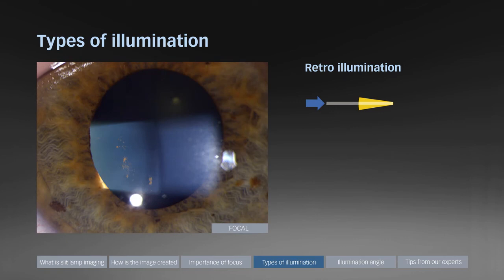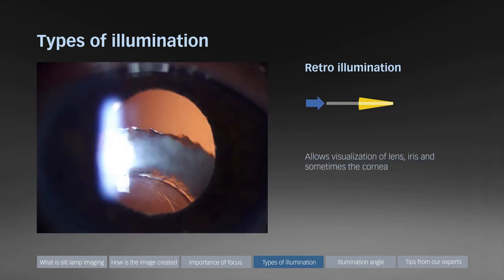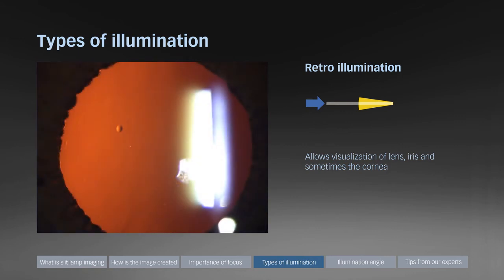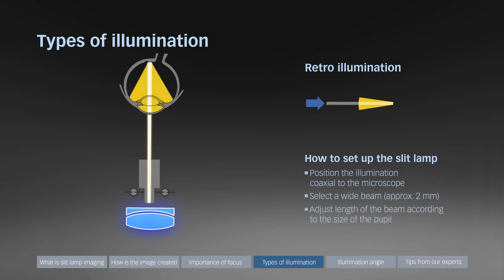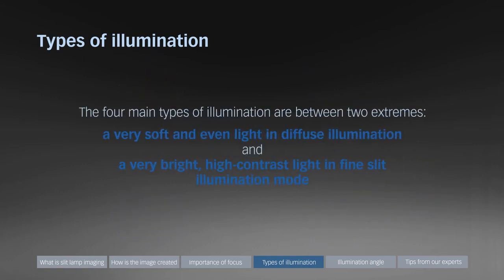Retro illumination uses light reflected from the retina coming towards the microscope. This can allow excellent visualization of pathologies that occur in the lens, the iris, and sometimes the cornea. To set up the slit lamp for retro illumination, position the illumination tower coaxial to the microscope, select a moderate beam width of between 1 and 2 mm, and adjust the length of the beam according to the size of the pupil. De-centering the slit beam towards the pupil margin optimizes the illumination and removes unwanted reflections from the center of the image. The four main types of illumination range between two extremes: a very soft and even light in diffuse illumination and a very bright high contrast light in fine slit illumination mode.